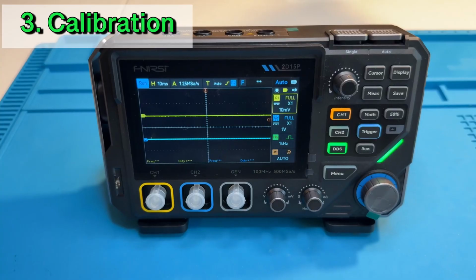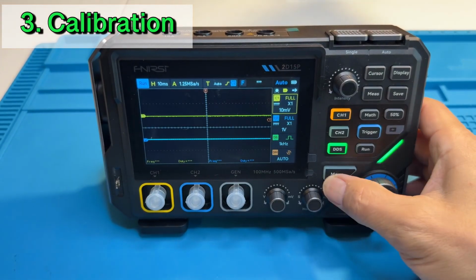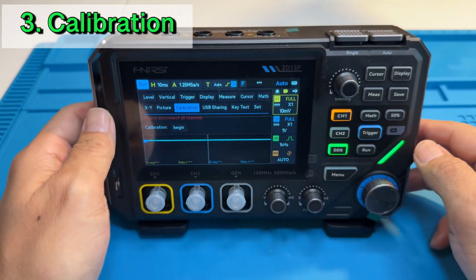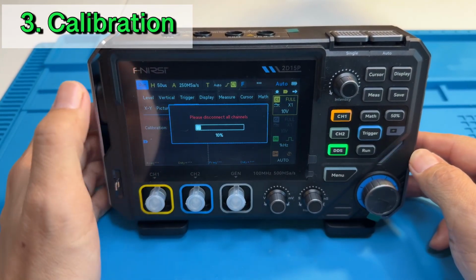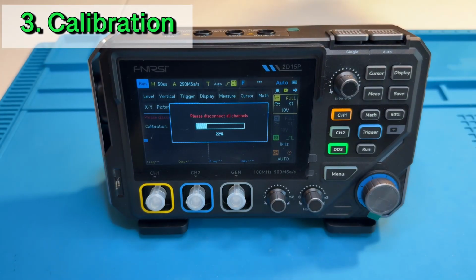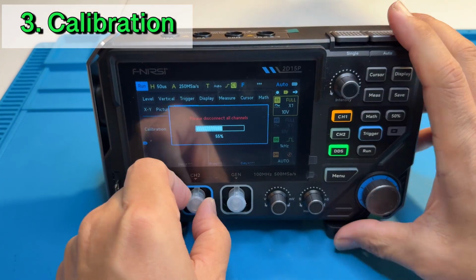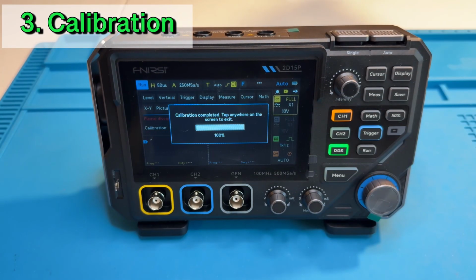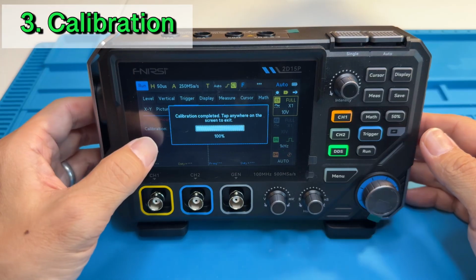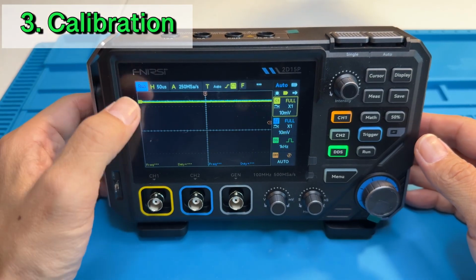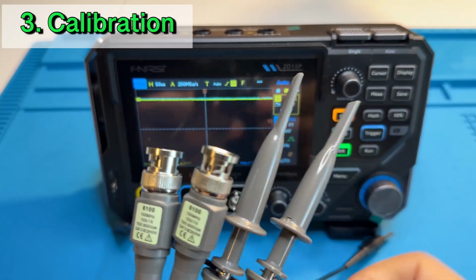Section 3, calibration. The first calibration is the scope calibration. Make sure there's no cable or wire connected to the scope. Just go to the menu, click calibration, click begin. Now the calibration process starts. This calibrates the scope itself, nothing else. And after you complete that step, we're gonna calibrate the probe.